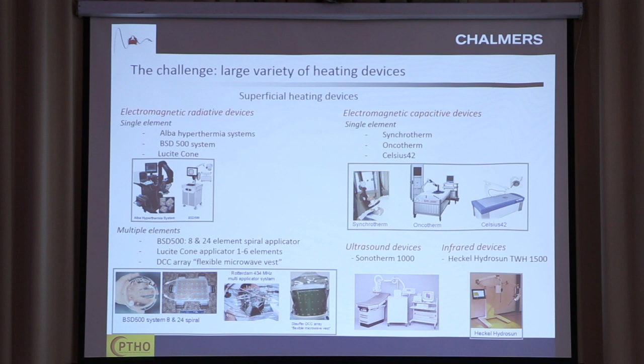And we needed to find a way to standardize the measurements of all these. And we came up with a criterion, which is called temperature rise for adequate heating. Here we have a fundamental requirement on the heating system, and we consider it to be adequate if a temperature rise of 6 degrees C can be achieved at 1 centimeter depth in a muscle phantom in 6 minutes. So you can see the rate is 1 degree C in 1 minute. And if the system is not capable of achieving this, it cannot be considered a good heating device, because if this temperature rise is impossible to reach in the phantom, you will never reach it in the patient with the perfusion.